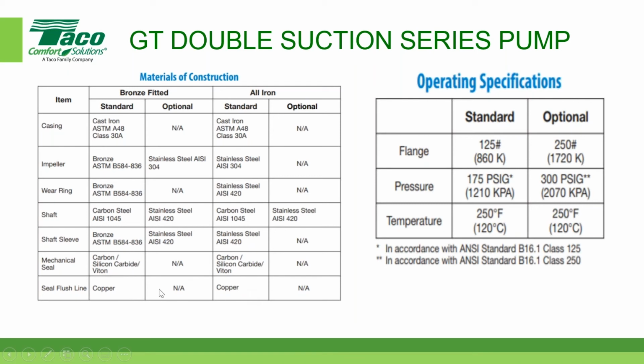It does come with a flush line - a copper flush line - so it keeps those chambers flushing, because they can heat up pretty quick and cause issues. You can see the working pressures and flange sizes on the right-hand side. You can get bigger flanges, similar to the base mounted pumps, the end suction pumps - I call them base mounted, but these are base mounted too, as you can see there's a big base for these pumps as well.